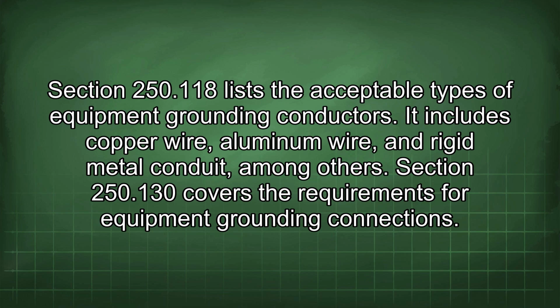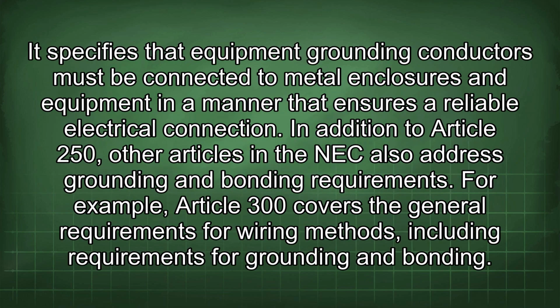Section 250.118 lists the acceptable types of equipment grounding conductors. It includes copper wire, aluminum wire, and rigid metal conduit, among others. Section 250.130 covers the requirements for equipment grounding connections. It specifies that equipment grounding conductors must be connected to metal enclosures and equipment in a manner that ensures a reliable electrical connection. In addition to Article 250, other articles in the NEC also address grounding and bonding requirements.